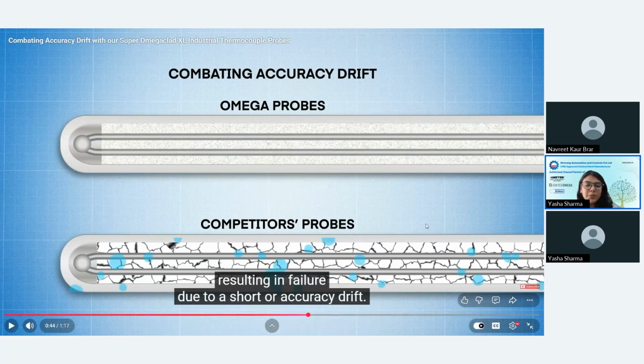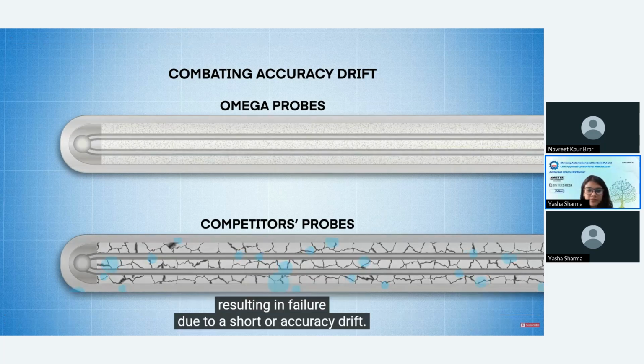So this is a very important phenomenon while manufacturing an RTD or thermocouple. The measuring part is here and we have a sheath. Between the measuring part and the sheath, magnesium oxide powder is filled as an insulation. But if the quality of this magnesium oxide powder has been compromised, then it will give you accuracy drift. Very fine magnesium oxide powder will be there, but if it is not fine, then there will be accuracy drift. That's what it is trying to make you understand. Failure due to a short or accuracy drift.